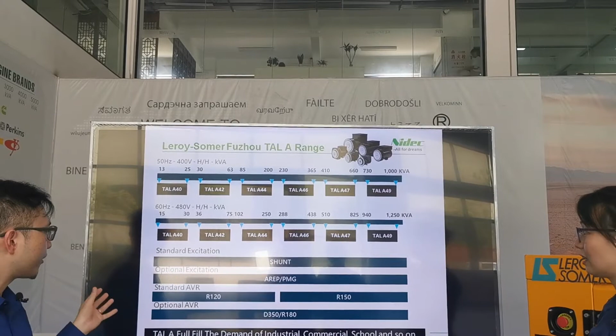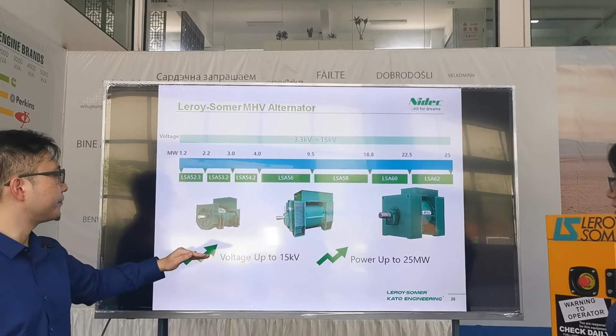For MHV alternators, medium high voltage, the majority of cases are mainly customization, so we just list the range here. Two numbers to highlight globally: for MHV, Leroy Somer can offer voltage up to 15,000 volts and power up to 25 megawatts. And from our Fuzhou facility, the voltage is up to 13.8 thousand volts, and the power is up to 15 megawatts.